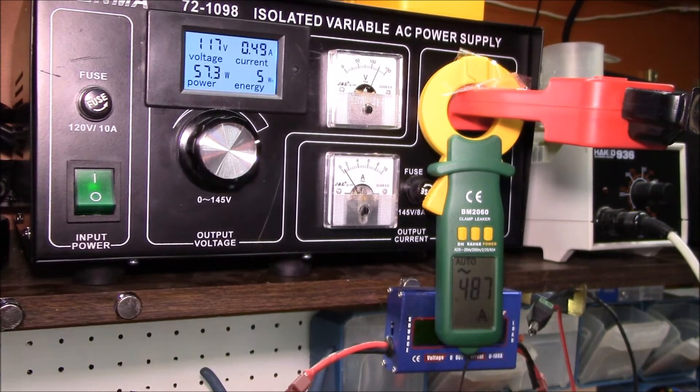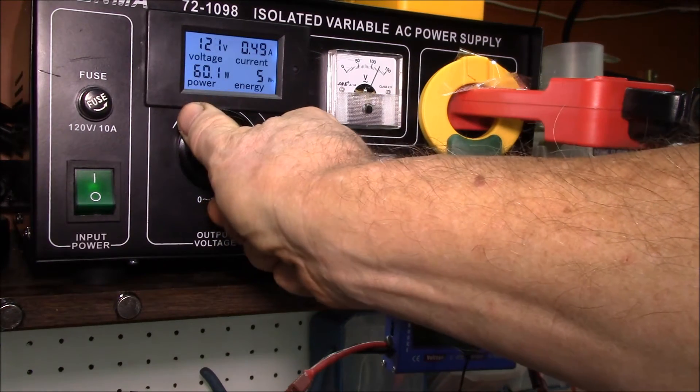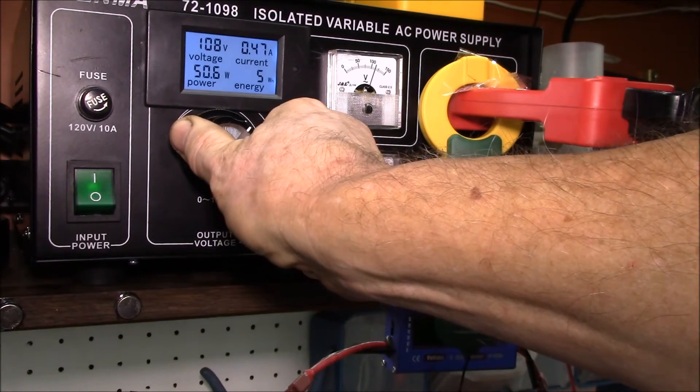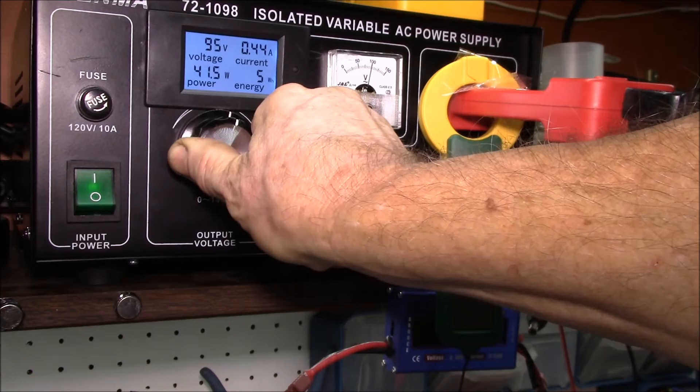Right now it's reading 498 milliamps and this meter is reading half an amp. Let's go down in voltage to drop the current. We can get down to where it just switches to four tenths - there we go, 400 milliamps, and that one's reading 401. I think that's pretty good.